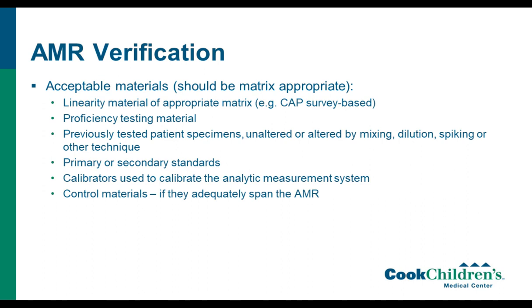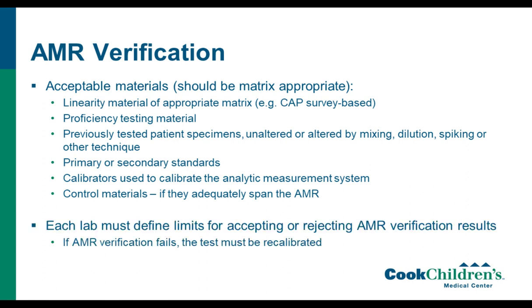Acceptable materials for AMR verification include, again, they should be matrix appropriate, but linearity material. So CAP does have a linearity panel for some of the viral load tests that you can use. Proficiency testing material, previously tested patients, primary or secondary standards, calibrators, or basically the difference between this and calibration verification is that you can also use control materials if they adequately span the AMR.